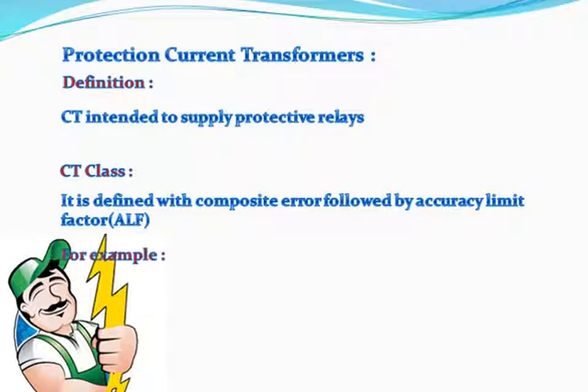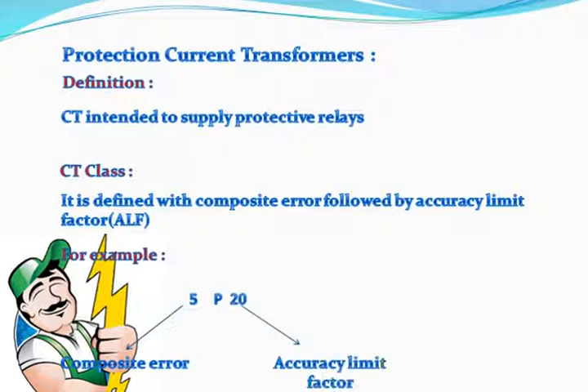For example, consider 5P20, in which 5 is the composite error, P denotes protection, and 20 is the accuracy limit factor.